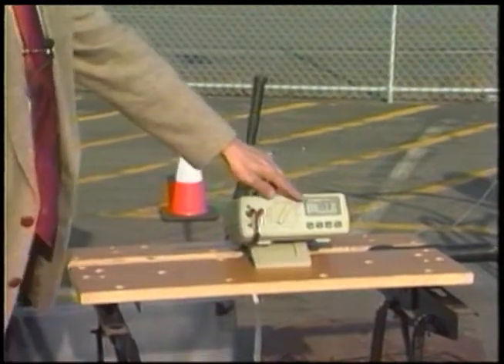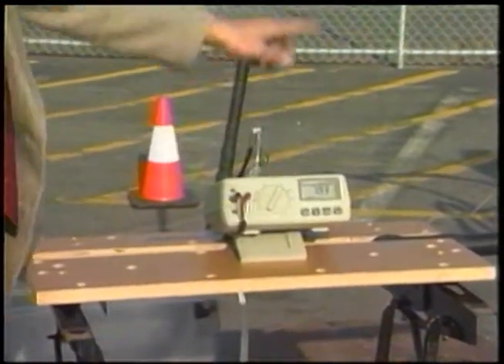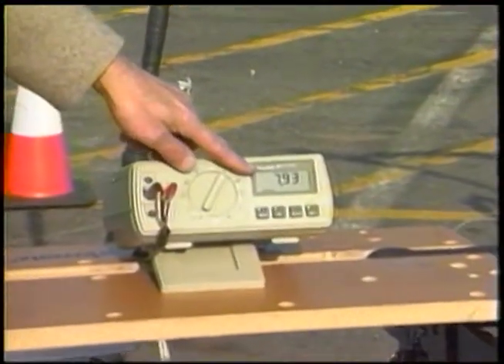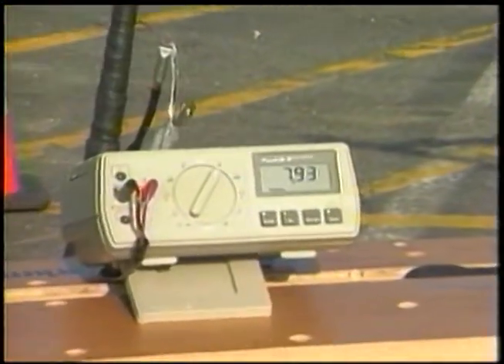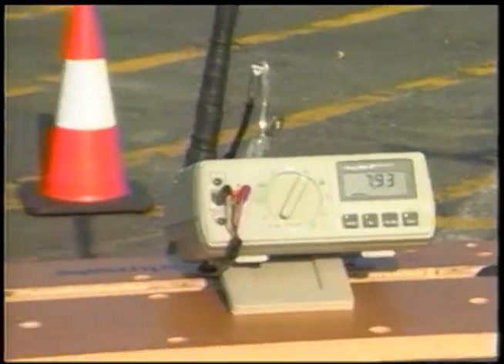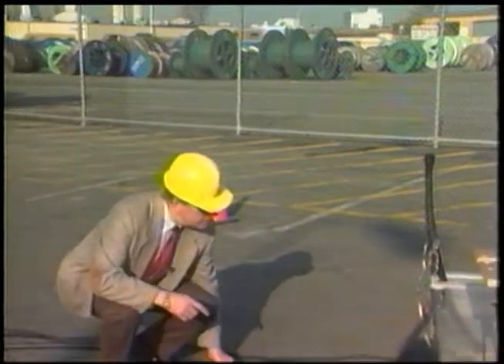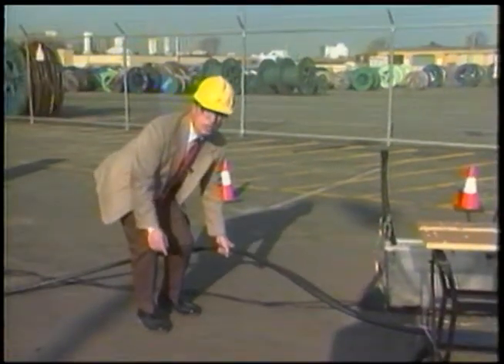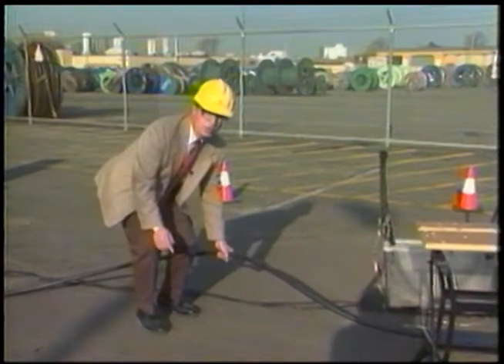The voltmeter now reads 7.93. That's a 1000-to-1 probe. That means we have 7,930 volts on the conductor of this cable. Now with 7,930 volts on the cable that we've energized with the transformer, I can pick up this cable without fear of electrocution because the cable is grounded.